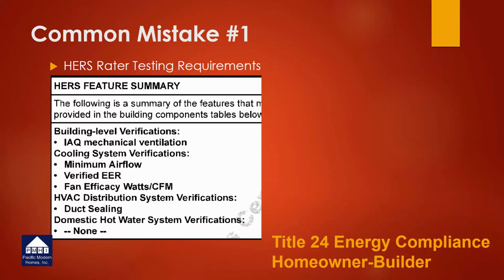This is a relatively small list of items that the HERS rater would typically need to do. So he will need to verify the indoor air quality ventilation fan and the minimum airflow on your heating and air conditioning system, and to verify the EER rating on the equipment, and to verify that the fan efficacy, or the fan efficiency, is appropriate. And he will be asked to look at duct sealing and testing it, both for installation and for leakage.